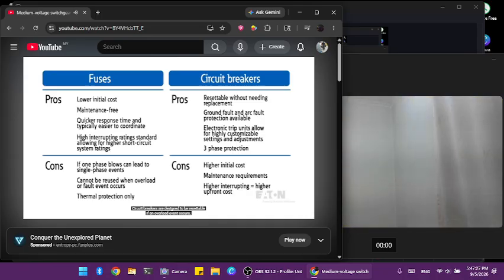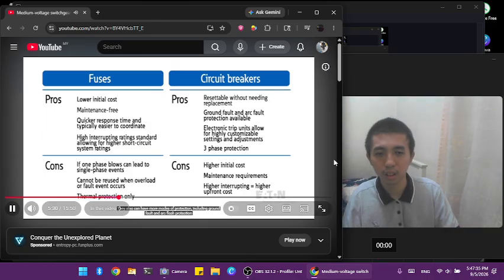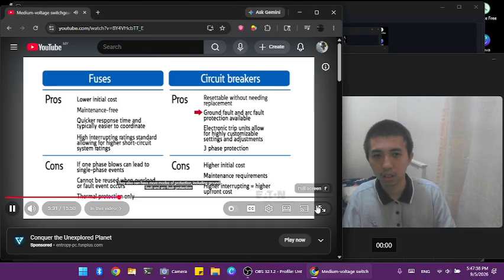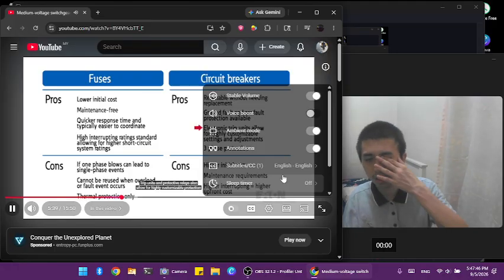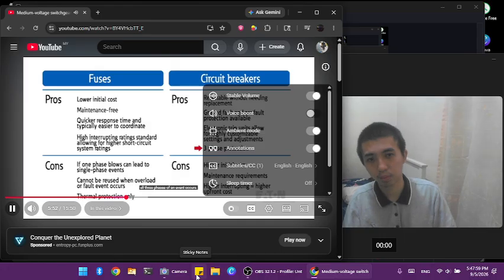Circuit breakers are designed to be resettable if an overload event occurs. They also can have more modes of protection, including ground fault and arc flash protection through electronic trip units or protective relays. Trip units and protective relays also allow for highly customizable protection settings, allowing for more adjustable coordination with downstream equipment. A circuit breaker provides 3-phase protection and will trip all 3 phases if an event occurs. They can also provide increased visibility and control through communications.